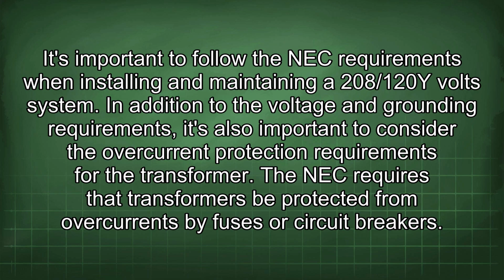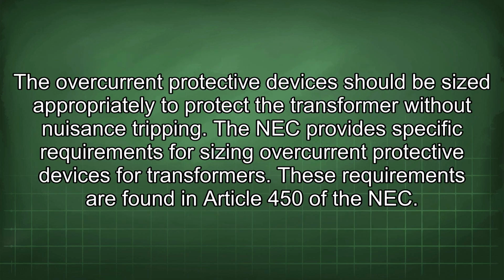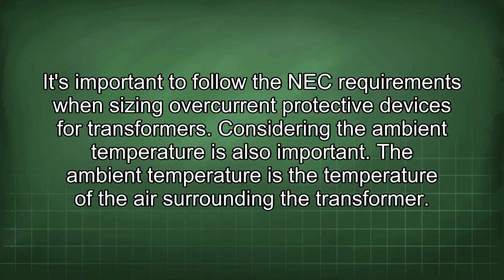208/120 volt system. In addition to the voltage and grounding requirements, it's also important to consider the overcurrent protection requirements for the transformer. The NEC requires that transformers be protected from overcurrents by fuses or circuit breakers. The overcurrent protective devices should be sized appropriately to protect the transformer without nuisance tripping. The NEC provides specific requirements for sizing overcurrent protective devices for transformers. These requirements are found in Article 450 of the NEC. It's important to follow the NEC requirements when sizing overcurrent protective devices for transformers.